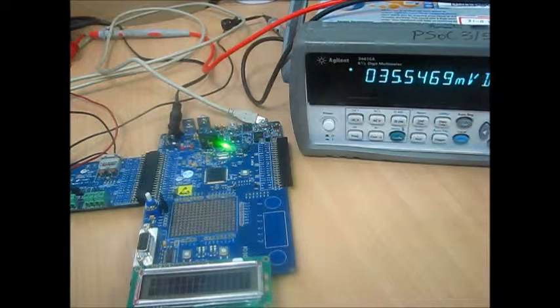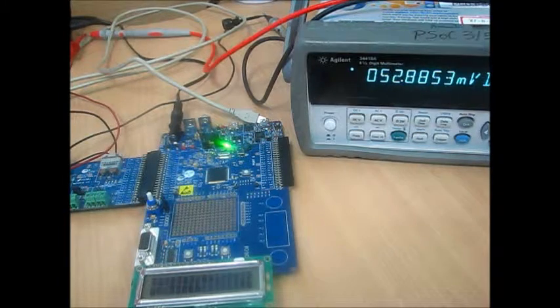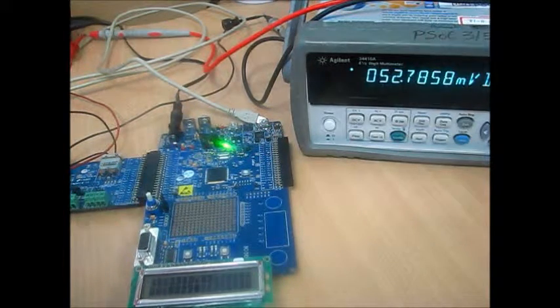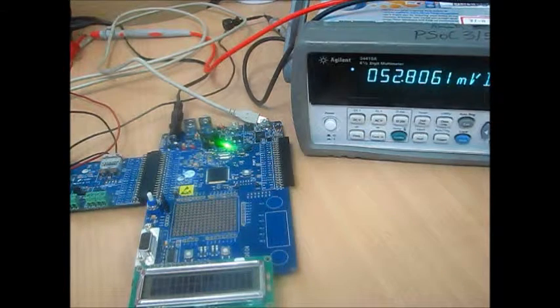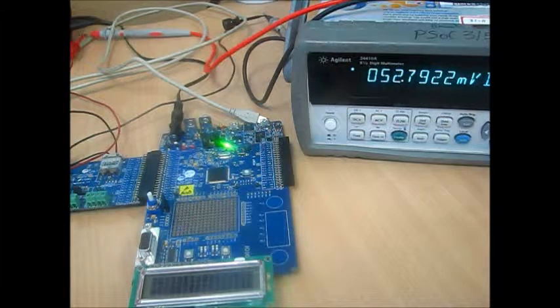Now I increase it to greater than 50 millivolts. It's 53 millivolts in this case, 52.8 millivolts, and the reading here is also very close. It's not significantly different either. Now, from this calibration, we've shown that calibrated accuracy is less than 0.1% or 0.5 degrees Celsius, whichever is greater. Thanks for watching the video.